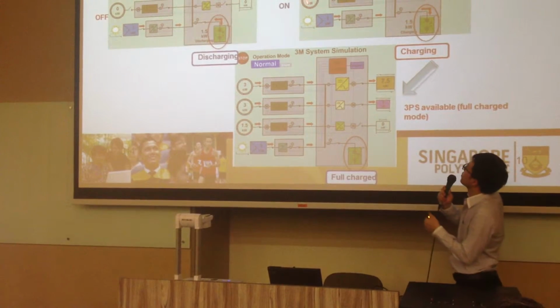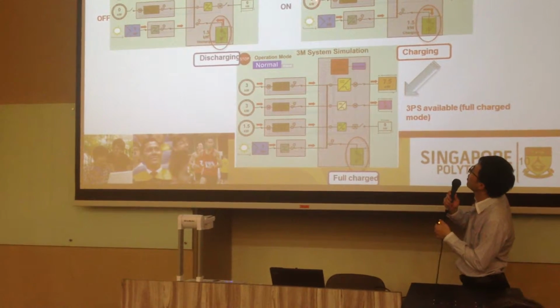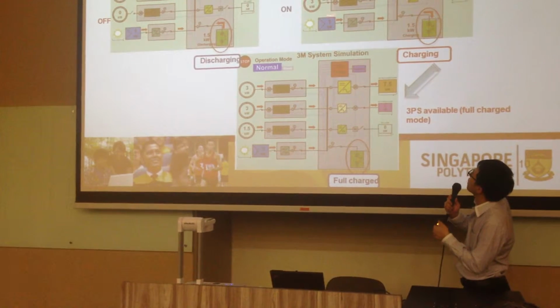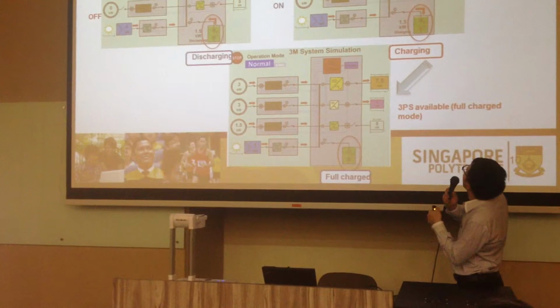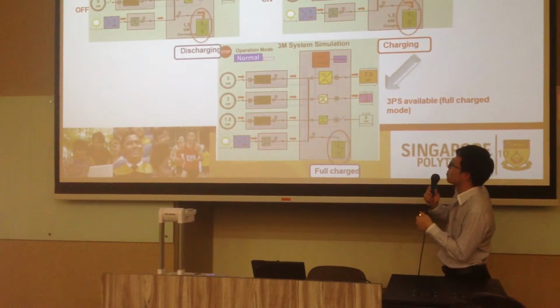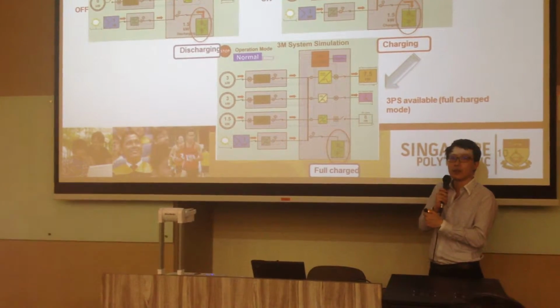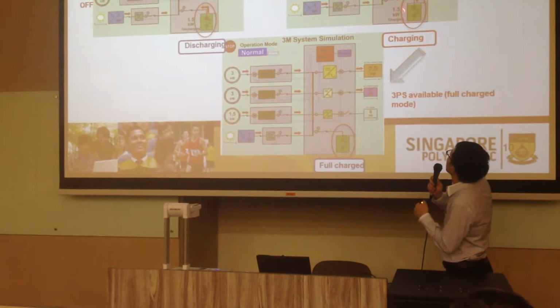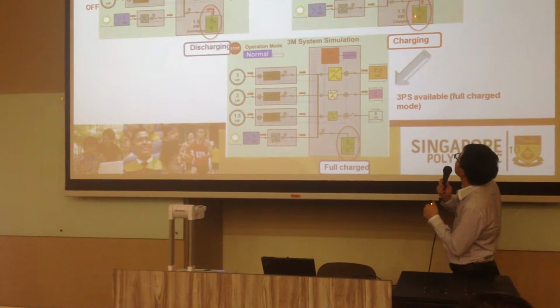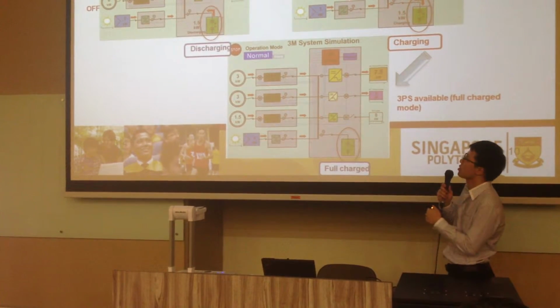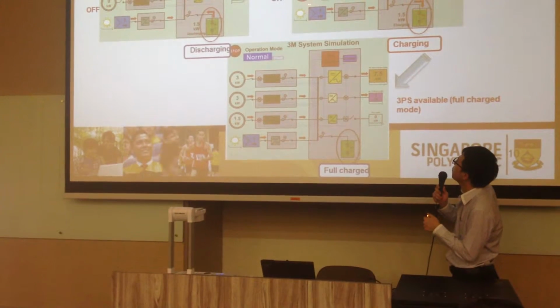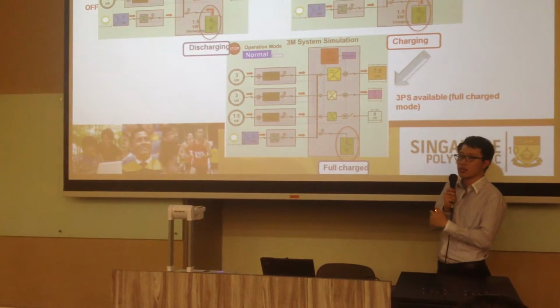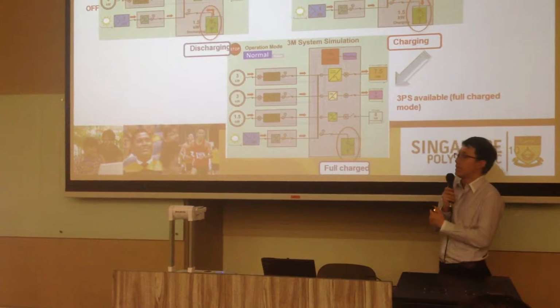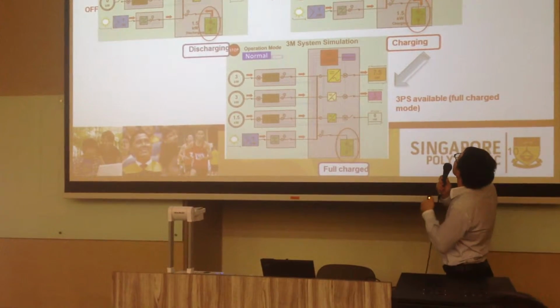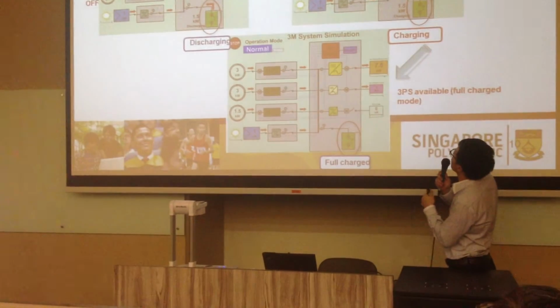But then a new power supply is triggered to join the power supply team. Each power supply's maximum output is 3 kilowatts. At that time, the battery is not fully charged, so the new one has to work under full power-on status to charge the battery and supply all the loads.